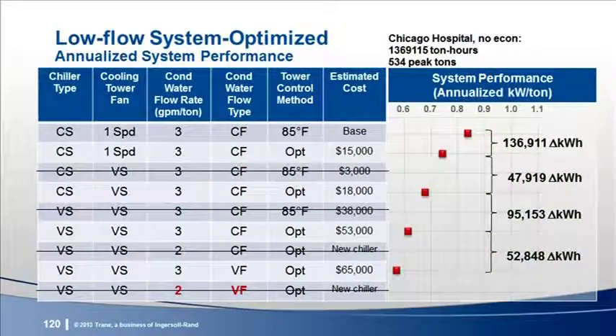So let's throw some hypothetical costs at it, but full disclosure, I don't do any pricing, so your costs will surely be different. If we assume a cost of $50 per kW for the drive, plus installation, putting the drive on the chiller costs roughly $35,000, installed on the 575-ton Climate 5A hospital. For the tower fans, less than $3,000 installed. If we can reuse the condenser pumps, putting drives on them would be about the same as the tower fans. If we can't reuse the condenser pumps and motors, it will cost quite a bit more.